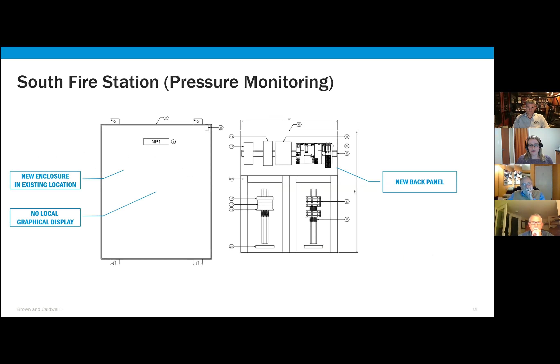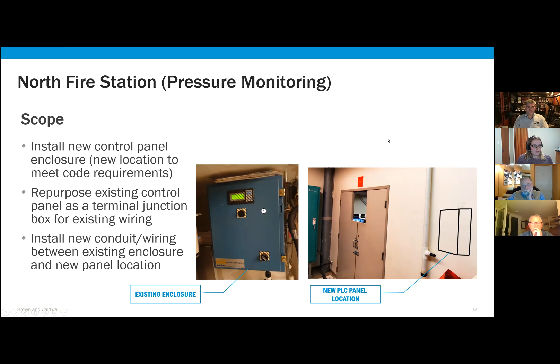At North Fire Station, this is the other pressure monitoring site. It's a little unique in that the existing control panel location doesn't meet electrical code requirements for working clearance. So because of this, the PLC panel is being relocated to a new location to bring it up to code. The existing panel is going to be repurposed as a terminal junction box. So all of the existing wiring lands here, and then the contractor will install new conduit wiring between this location and the new panel location, which is shown here on the right. And the control panel layout is identical to what we showed at South Fire Station.